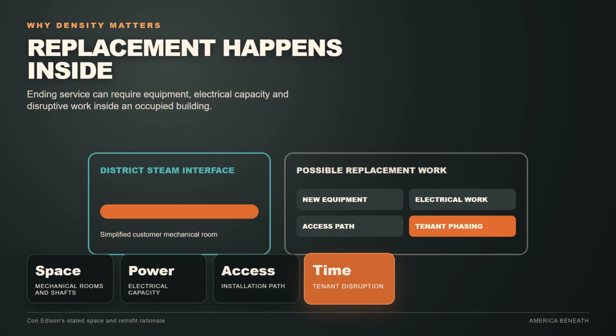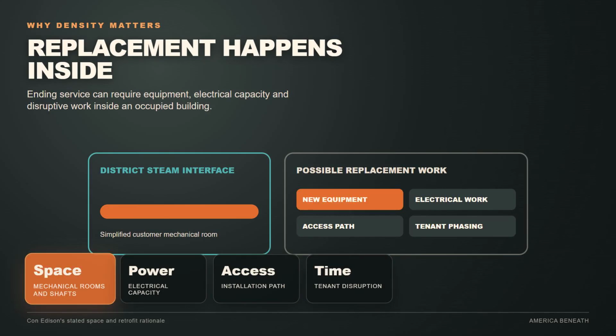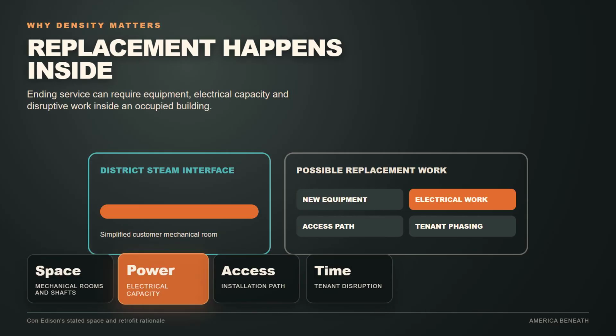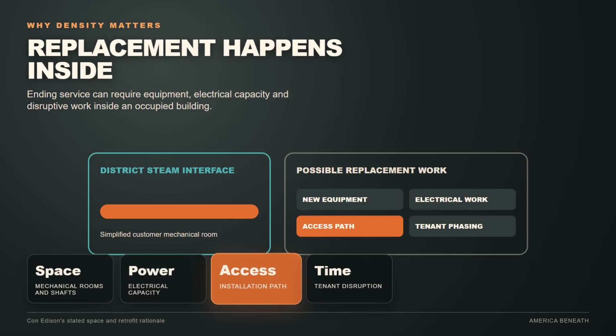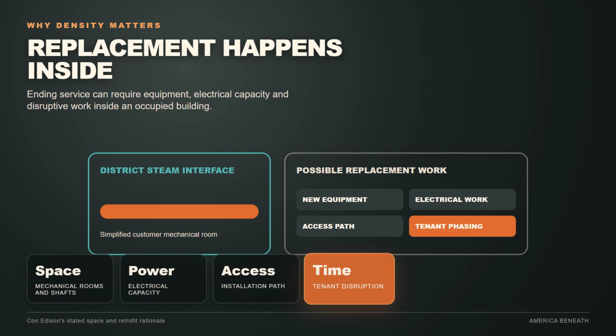District steam moves part of the production problem outside the customer building. The property still needs equipment to receive and use the steam, but it may not need the same on-site plant that would be required to produce equivalent thermal energy from scratch. Con Edison argues that this can preserve building space and avoid some of the disruption associated with a deep retrofit. That is the operator's case, not proof that steam is cheapest or best for every property. Different buildings can reach different answers, but the argument explains why an owner cannot evaluate the connection by looking only at the age of the network.